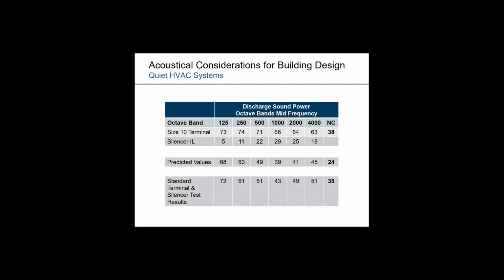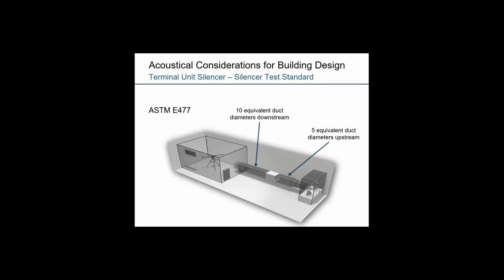The problem with this prediction is that through testing and development, we've found this isn't typically the case. Taking a silencer and a terminal unit that weren't intended to be close coupled together can result in higher overall discharge sound levels, not the ideal predicted levels. And really the reason for this is that the ASTM standard I introduced earlier has equivalent empty duct diameters upstream and downstream of that silencer. It's tested under almost ideal conditions without any real system effect applied to it as part of the standard.